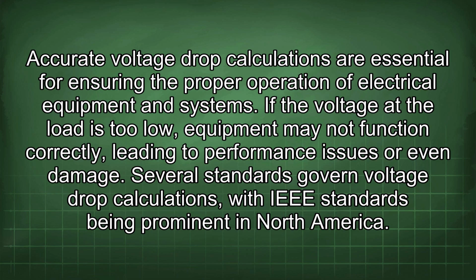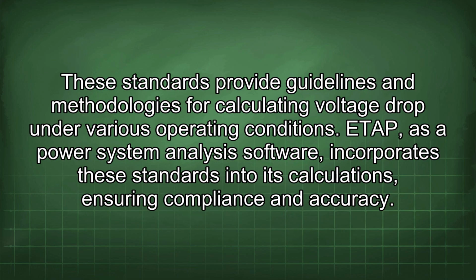If the voltage at the load is too low, equipment may not function correctly, leading to performance issues or even damage. Several standards govern voltage drop calculations, with IEEE standards being prominent in North America. These standards provide guidelines and methodologies for calculating voltage drop under various operating conditions. ETAP, as a power system analysis software, incorporates these standards into its calculations, ensuring compliance and accuracy.